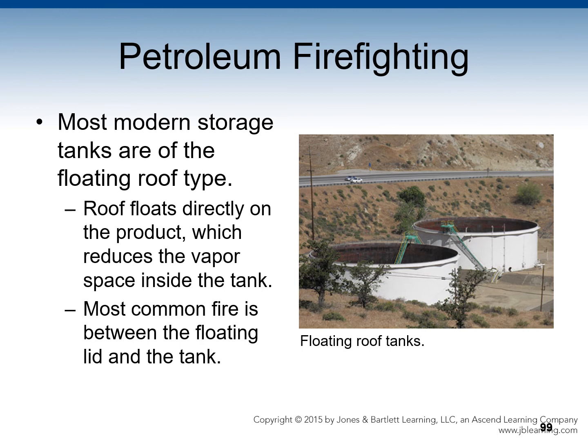When large amounts of water are pumped onto the lid, it can cause it to sink, increasing the burning surface area greatly. The two methods most commonly used on a seal fire are attack lines using a foam or dry chemical extinguishers. If the tank is equipped with a plumbing system for foam application, it should be designed with a dam to keep the foam applied over the area of the seal.